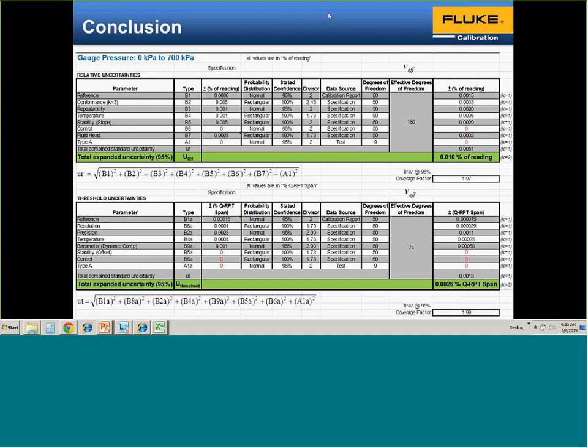Is there a head or fluid correction for a pneumatic controller or deadweight tester, with reference to the head correction? I think in our Q-RPT, our piston gauge tech note, it's not considered because it was assumed that you can bring the device under test to the reference level of the piston gauge. If you're doing that, you should always leave the component in your budget though, and put a 0 there, or put a comment that you considered it but it's not significant.